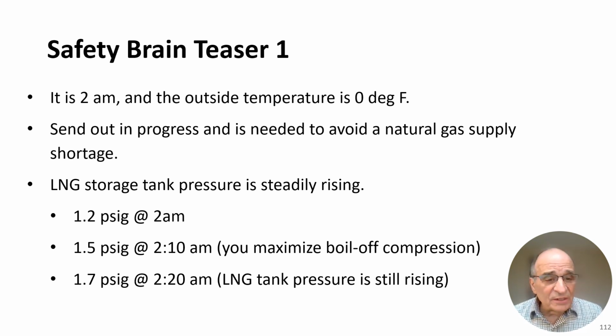It's now 1.7 psig and it's 2:20 a.m. in the morning. The tank pressure is still rising. Your concern is the tank relief valves are going to lift. What could be wrong? That's for you to consider and ponder. After all we've gone over and discussed in this lesson, you should be able to come up with several scenarios that could be at it.